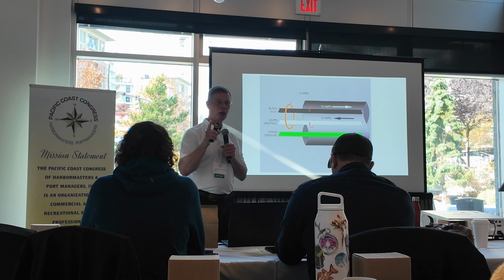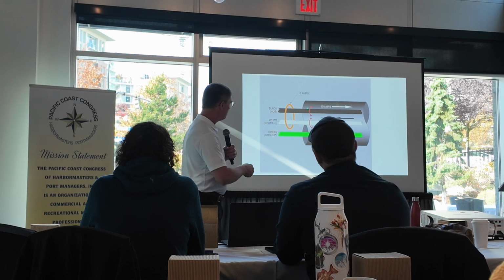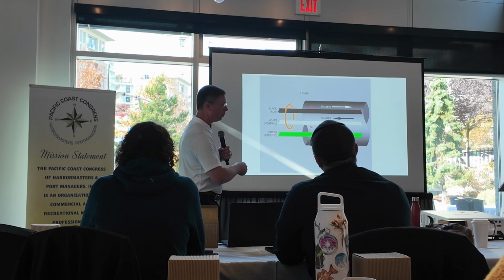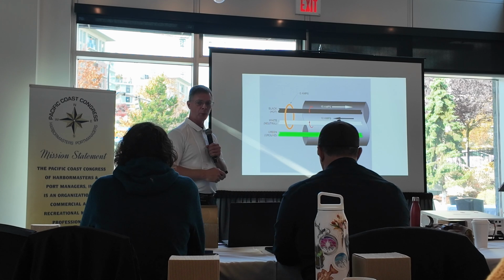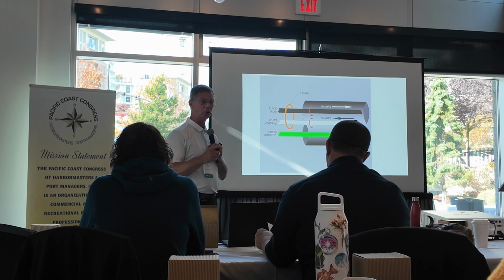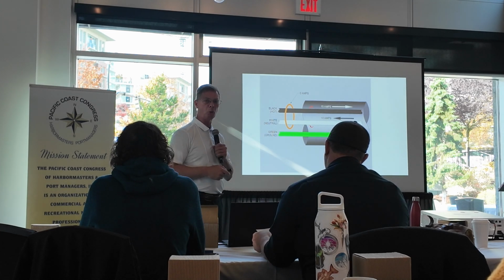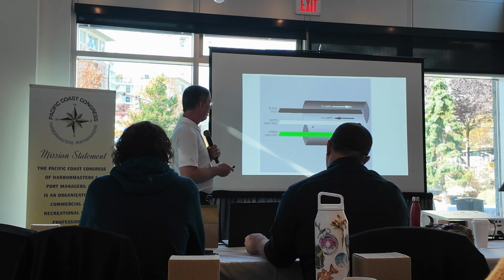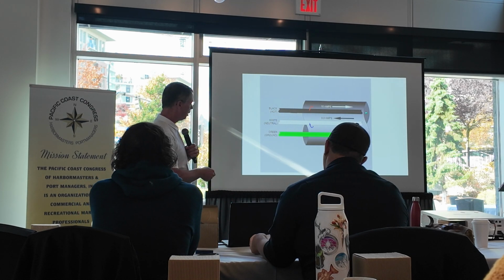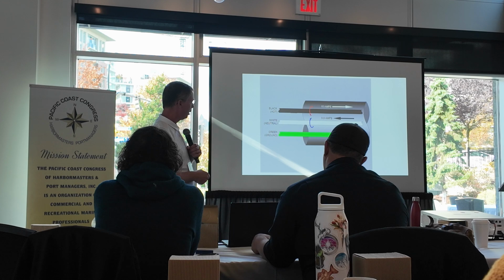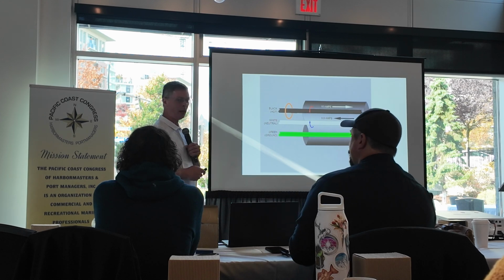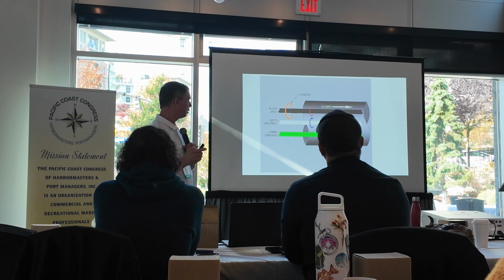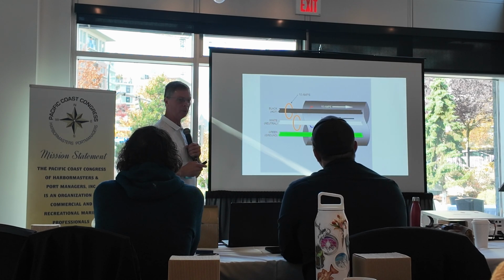Very, very important to understand that, because this is the CT that I've been talking about. Remember all the CTs that we've been talking about? That's how ground faults are measured, in this fashion through the magnetic fields. So in this case, I've got 10 amps going and say I've got 9.9 amps coming back. If I clamp around the black wire, what would I measure? Clamp around the white wire, what would I measure? 9.9 amps. Clamp around both of them, 100 milliamps.